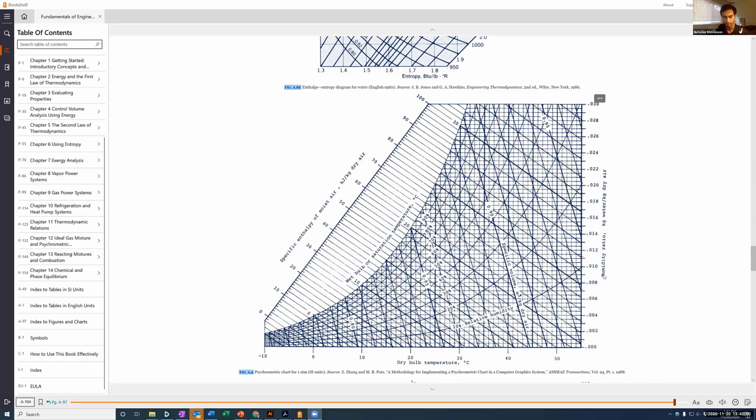Yeah. All right, so Nicholas is saying that I'm starting here at 7.5 and I'm going to stay on that horizontal line, either left or right. So which side am I going, Nicholas? Left. I'm going left because that's the direction where the enthalpy is dropping, and I'm sucking that 20 kilojoules out of the air. So the enthalpy of the air has got to drop. Correct. Exactly. So I'm going to move to the left, which means that the relative humidity is increasing until eventually I hit that point right there.